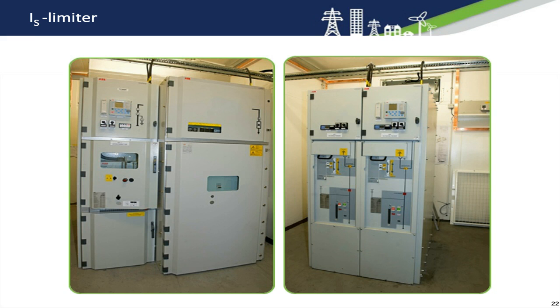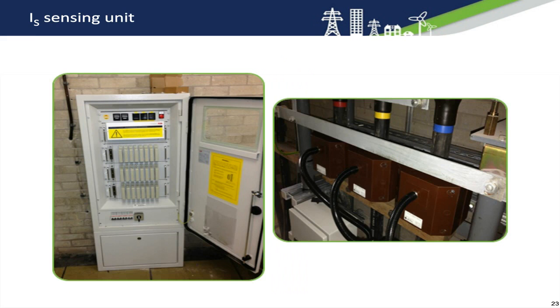IS sensing units. In order to trial the IS technology at more sites but at a reduced cost, we have utilised the IS sensing units at 5 sites. These units detect and operate after a fault exactly the same as an IS limiter, but without the actual cost of the IS limiter. This approach allows us to trial the effectiveness of the technology across a wider region. The photo on the left is an IS unit installed on our substations, and the photograph on the right is the IS sensing CTs installed at one of our substations.